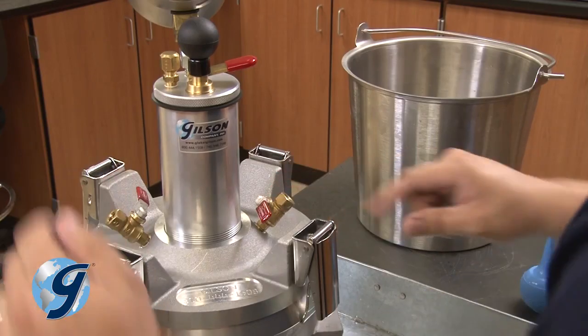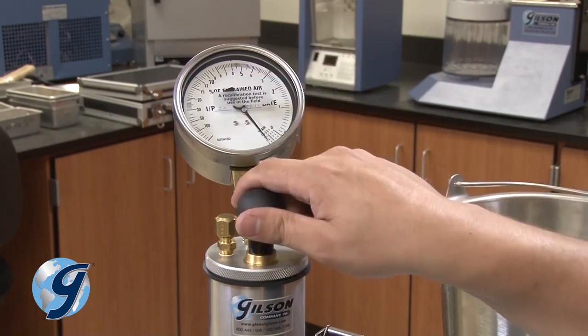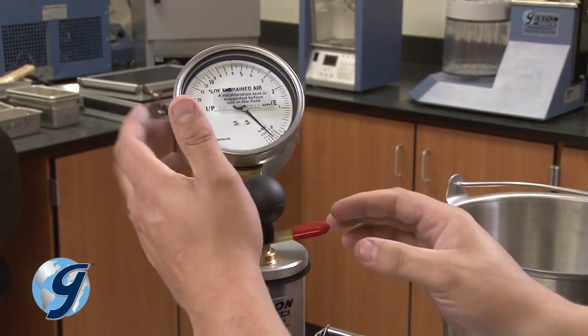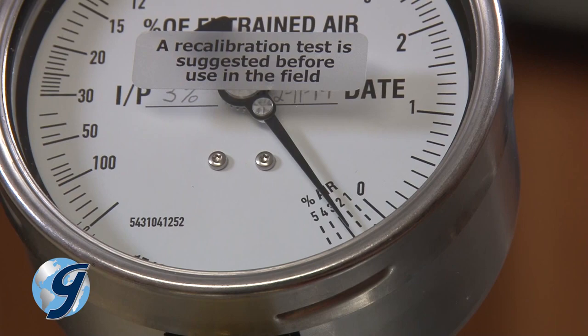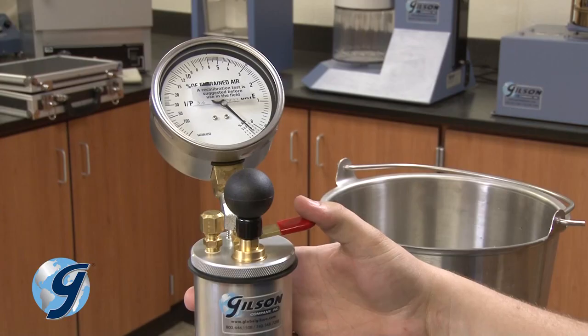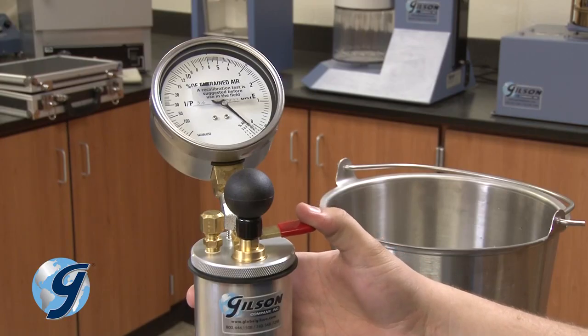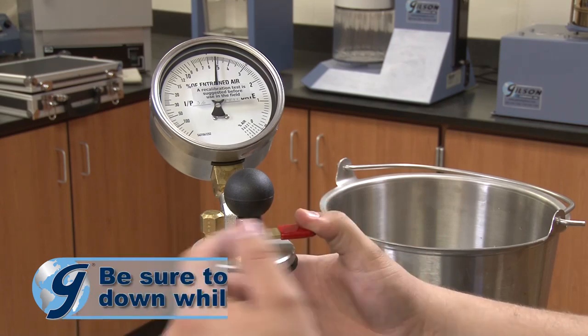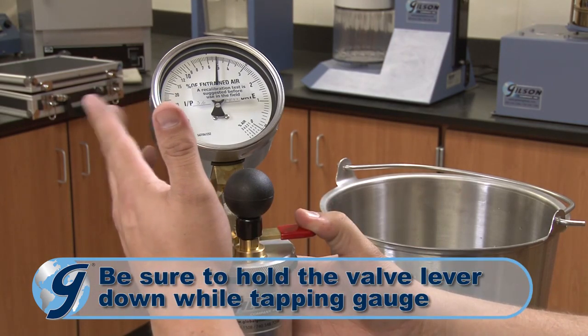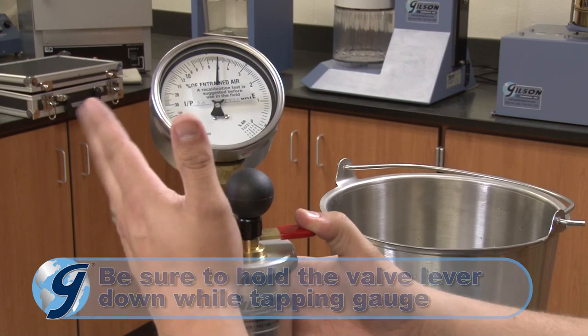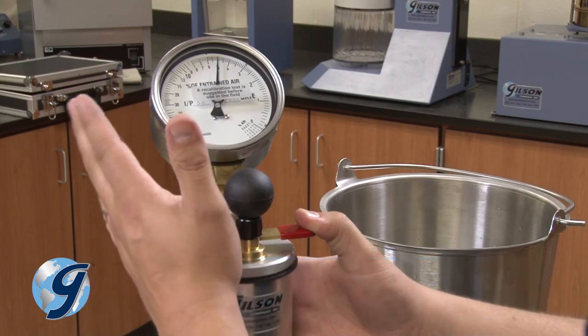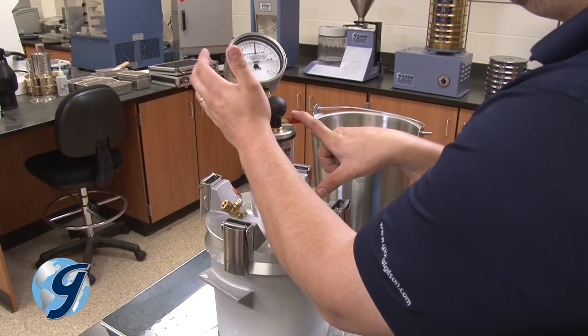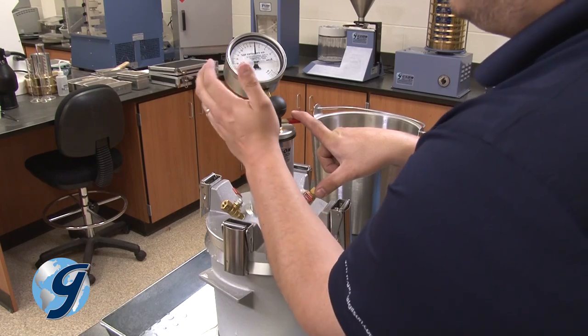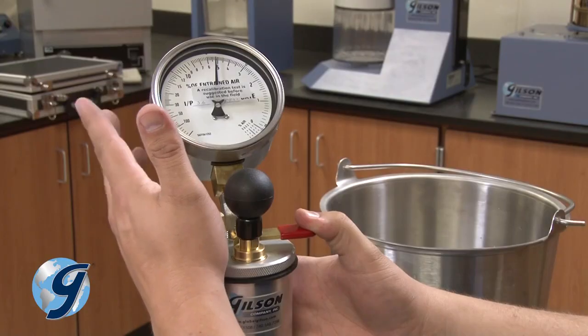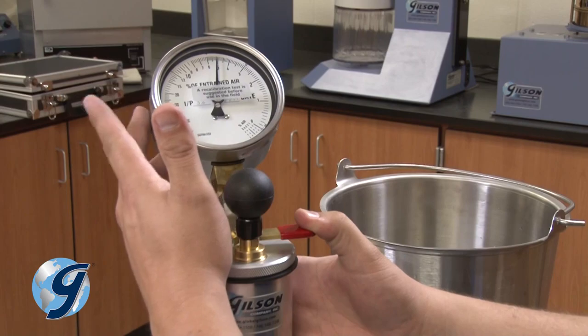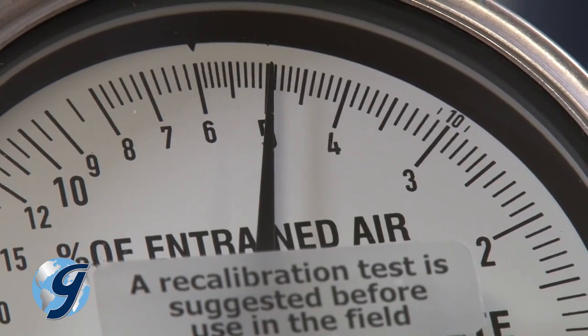Now, close both petcocks and pump the unit back up to the predetermined initial pressure mark, making sure to lightly tap the gauge body until it stabilizes. Next, press down on the needle valve lever to exhaust the air into the base, making sure to hold the lever down while again lightly tapping the gauge body until the reading stabilizes. The gauge should read plus or minus 0.1% from the correct air content as determined by the calibration of the calibration vessel. In this demonstration, the value is 5%.